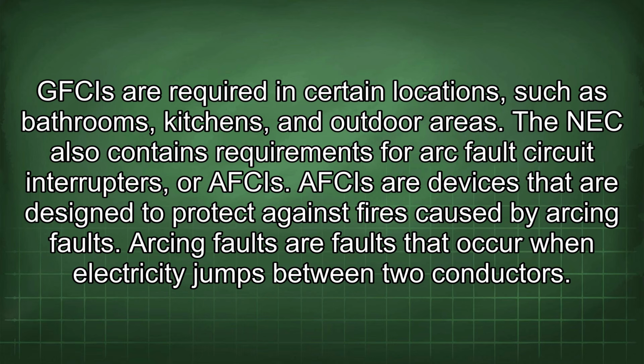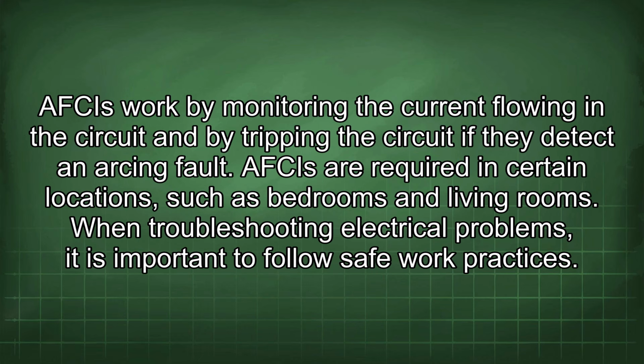The NEC also contains requirements for arc fault circuit interrupters, or AFCIs. AFCIs are devices that are designed to protect against fires caused by arcing faults. Arcing faults are faults that occur when electricity jumps between two conductors. AFCIs work by monitoring the current flowing in the circuit and by tripping the circuit if they detect an arcing fault. AFCIs are required in certain locations, such as bedrooms and living rooms.